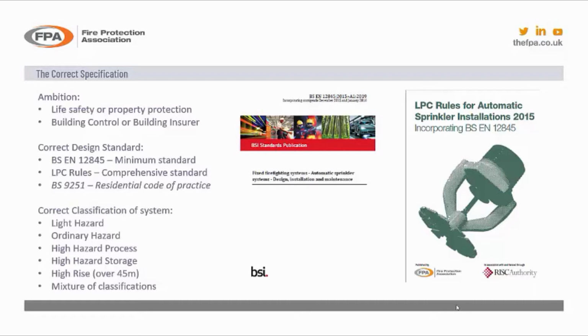We also have high rise, buildings over 45 metres, and that's measured from the centre line of the pump to the highest sprinkler, or from the lowest sprinkler to the highest sprinkler, and this is pretty much representative of high rise office buildings or mixed use buildings. As we've got there, a mixture of classifications. This could be a building that's got, maybe on the ground and first floor, some retail areas. On the second floor to the 5th floor could be office, and from the 5th floor upwards could be residential. We've got mixed use buildings.